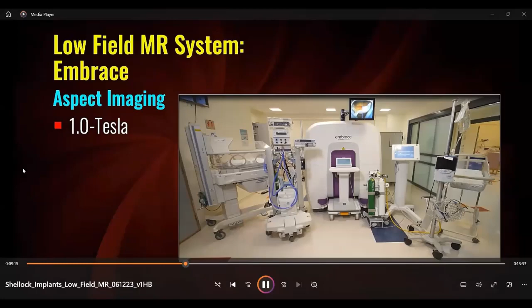Because of its unique design, there are no issues related to ferromagnetic objects or the need for MR conditional patient support equipment. By way of example, take a look at the Embrace scanner installation in a typical neonatal ICU. Note the presence of a standard incubator, conventional physiological monitoring equipment, a ventilator, an infusion pump, and steel oxygen tanks, all positioned in close proximity to the neonatal MR system.